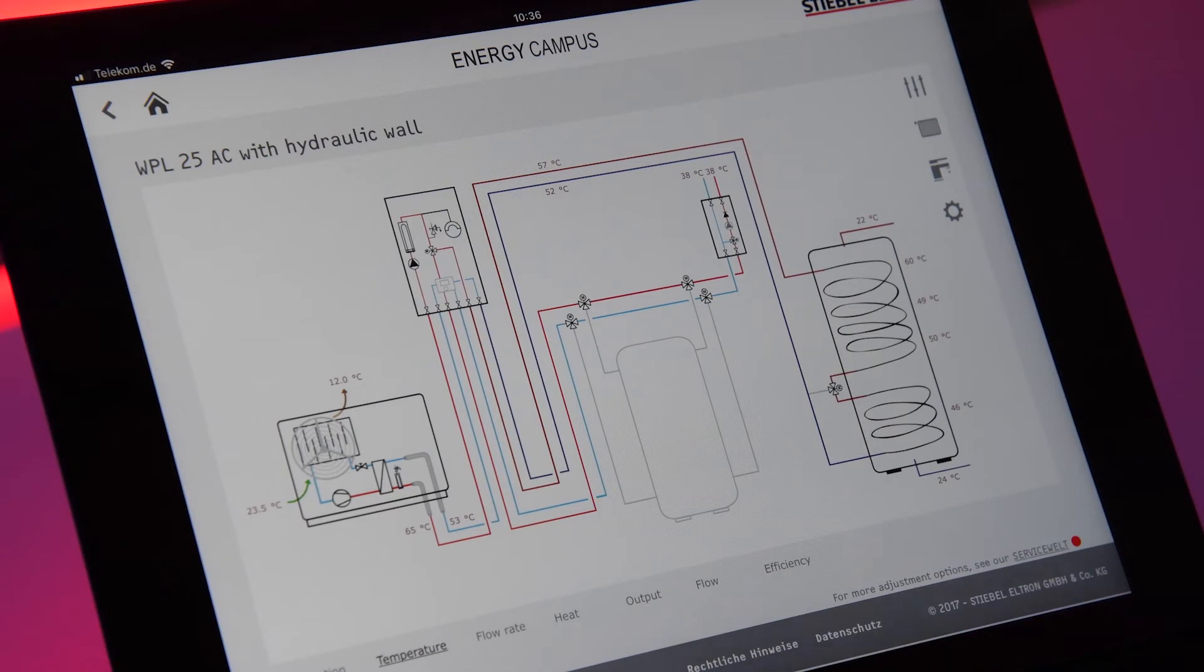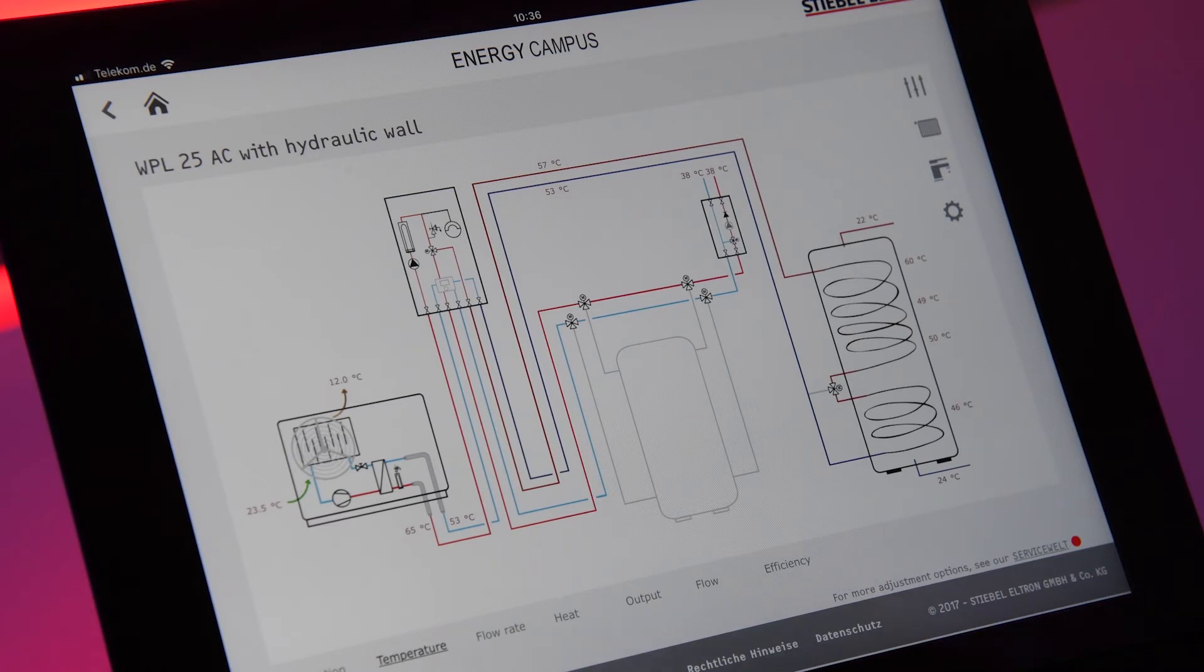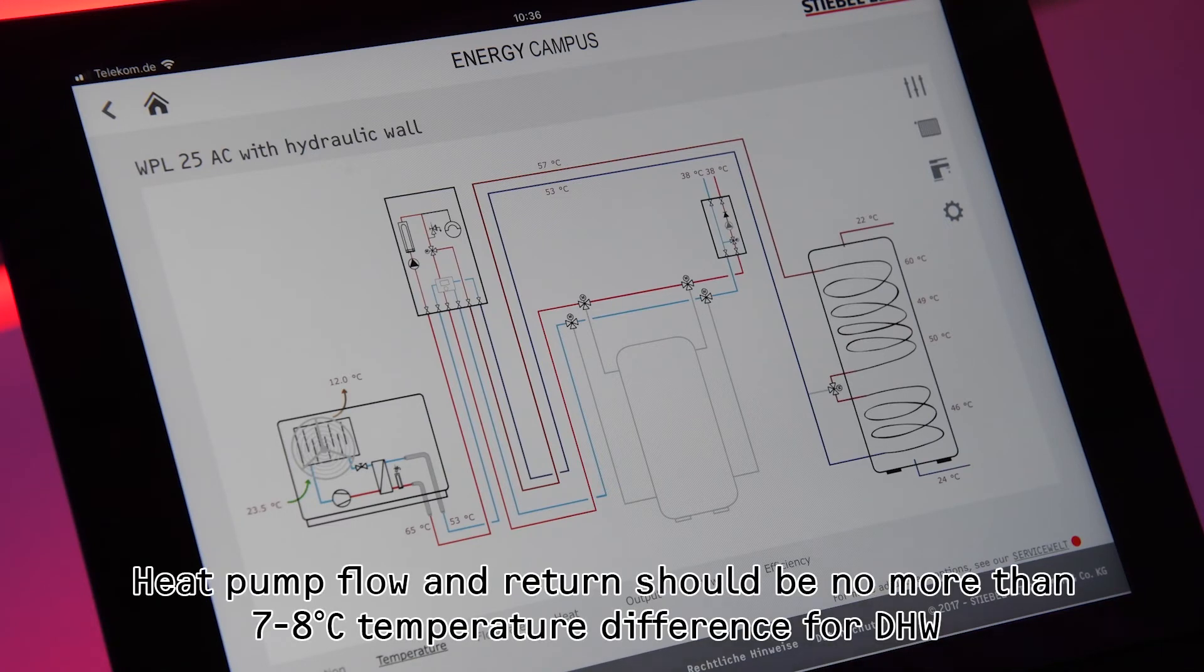12 Kelvin delta T on the heat pump is from the beginning already too much. So usually we will try to work with 5 to 7, in domestic hot water maybe 7 to 8, but that should be the maximum.